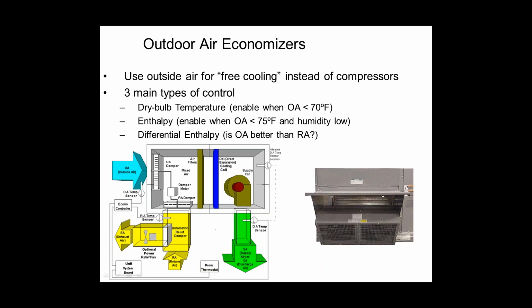But we're also going to check to see if the humidity is high or low. So if the humidity is low and it's less than 75 degrees, yeehaw, economizer time. If the temperature's high or the humidity is high, forget it. We're not doing it at all. Right? So enthalpy economizers allow us to do a few more hours a year of economizing because we're being smart and checking the humidity too.